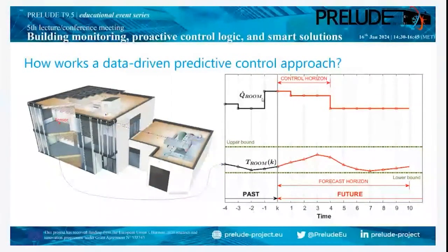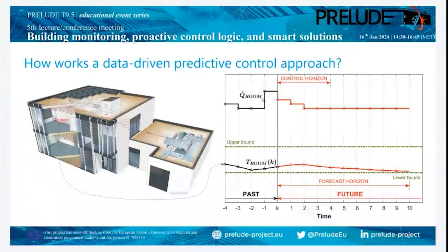But the question is: is there another solution where we also ensure the thermal comfort and where we don't need as much power as you see on this slide? The data-driven predictive control approach always needs an objective. For these slides, I use the objective that we want to minimize the energy demand for the next 10 time steps, for example. If we look toward the optimal solution, we see that we need less heating energy to ensure that thermal behavior in the zone for the next 10 time steps.